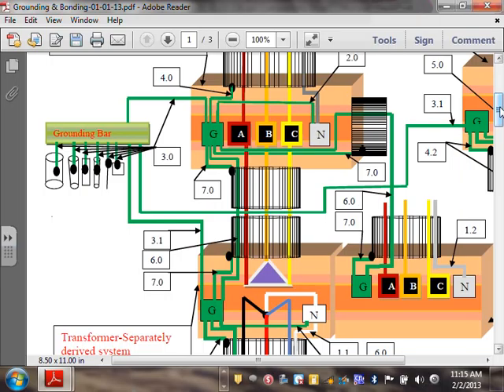Because in the US, we run receptacles at 120, right? So we have to have another transformer in most of the commercial industrial buildings. Okay, here's my transformer. Right inside the transformer, you're going to have a ground bar and a neutral, or the X0 point of the transformer. Now here, we created a new neutral, and I have no choice. I have no option to tie the neutrals together because I have two voltage systems. It's not the same voltage, so you have to bond your neutral to the ground. Every time you create a new neutral, you have to bond the new neutral to the ground.